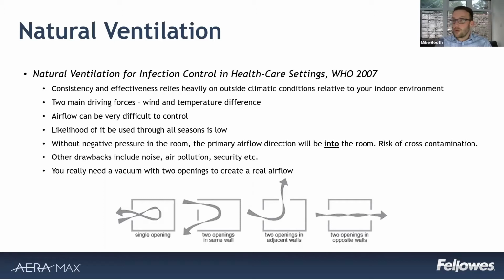The other thing that we were able to show with some simulations that I will come on to in a short while is that if you're not careful about how you approach the topic of natural ventilation, you can end up removing the problem from the room, but actually moving it to other parts of the building. So if you imagine an open window and an open door within a facility, the airflow movement is typically going to be air into the room and then that air into other parts of the facility, which is certainly not what you want, especially if you've got staff or patients spending time in other parts of the facility as well.